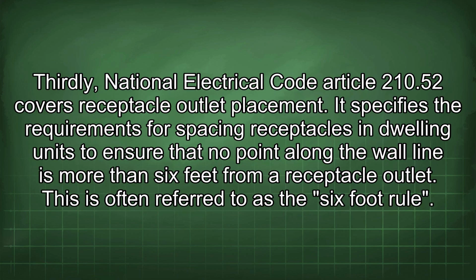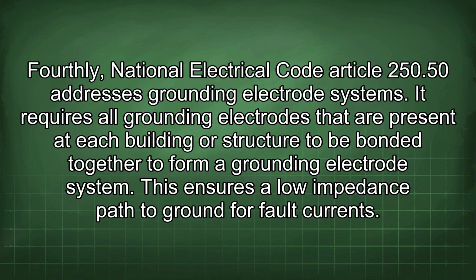Thirdly, National Electrical Code Article 210.52 covers receptacle outlet placement. It specifies the requirements for spacing receptacles in dwelling units to ensure that no point along the wall line is more than 6 feet from a receptacle outlet. This is often referred to as the 6-foot rule. Fourthly, National Electrical Code Article 250.50 addresses grounding electrode systems. It requires all grounding electrodes that are present at each building or structure to be bonded together to form a grounding electrode system. This ensures a low impedance path to ground for fault currents.